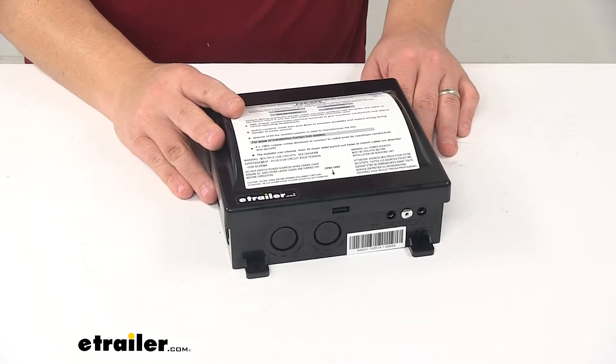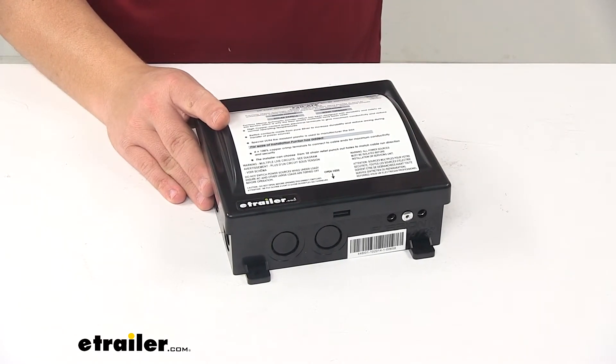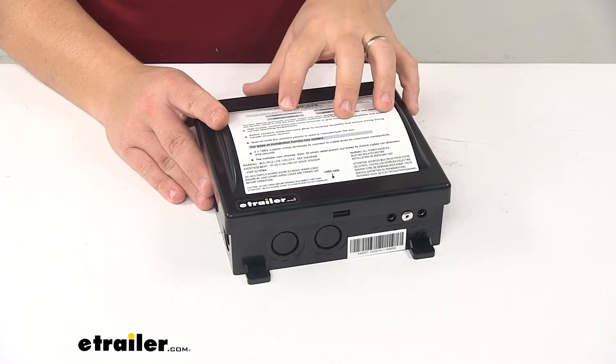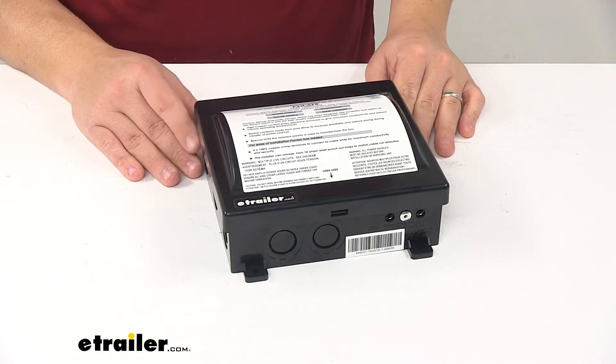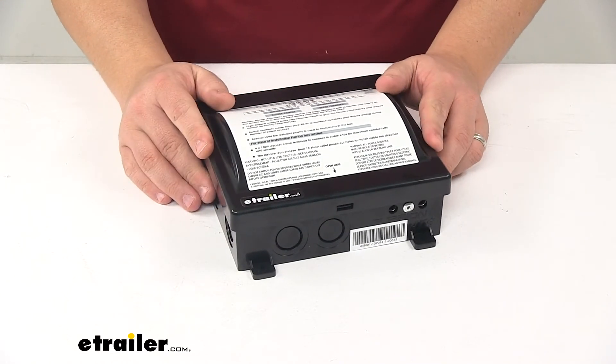The rated amperage is 30 amps, rated voltage is 125 volts AC, rated frequency is 60 hertz, maximum wattage is 3,750 watts, and the short circuit rating is 5,000 amps. That's going to do it for today's look at the Furrion Automatic Transfer Switch.